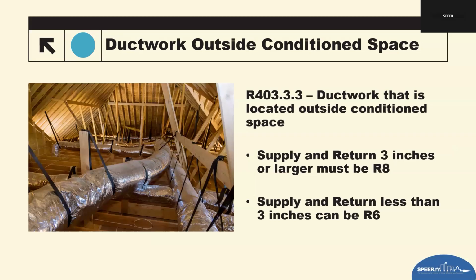That's what a third party is required to do. Building officials will do the same. R8 flex duct outer jackets are usually clearly marked. If it's not labeled, treat it as non-compliant because you really don't know. But sometimes it's got a faded label or a faded mark from the manufacturer. Just make sure that you try to find that. If you can't, usually ask the installers for a spec sheet for the ductwork.